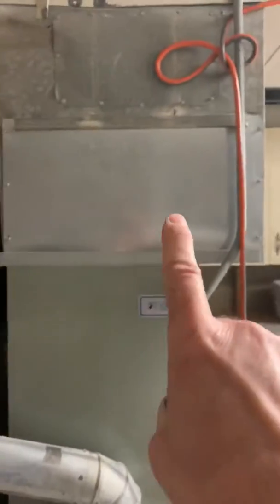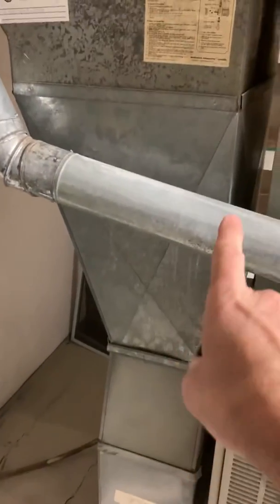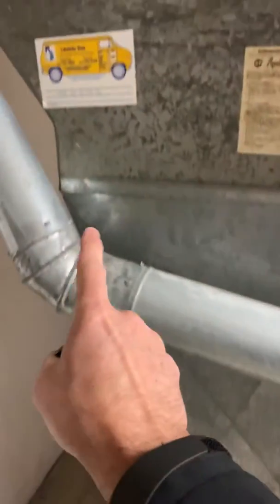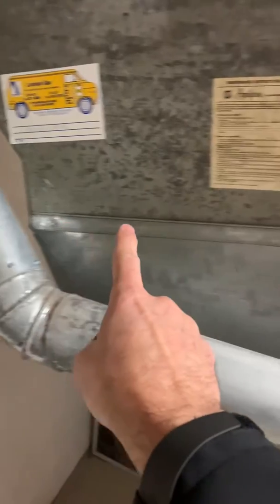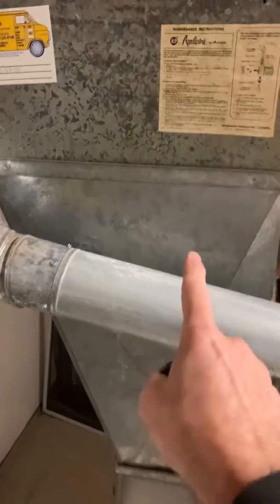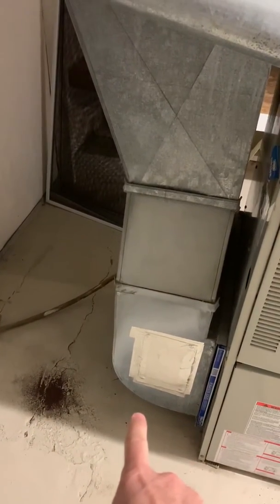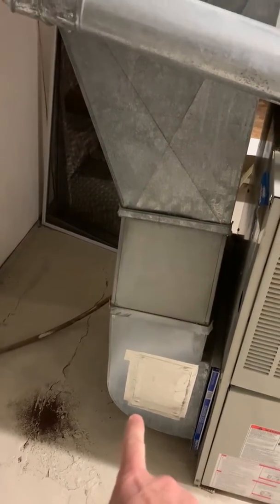To make up the difference in height on the return — we have a pretty large return. We're looking at coming down about 56 inches, which allows for our five-inch filter to come in between here. From that point, 13 and a half inches over puts us right at our seven-inch mark to allow for the filter. To the ground is about 56 or 57 inches; I've got it written down, so we'll make it just a hair shorter so we're not scraping.